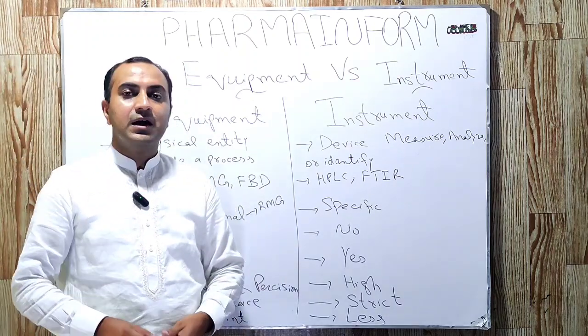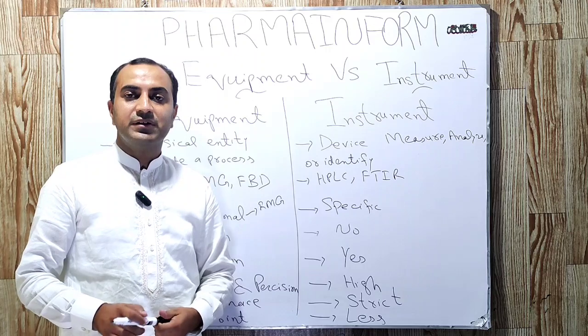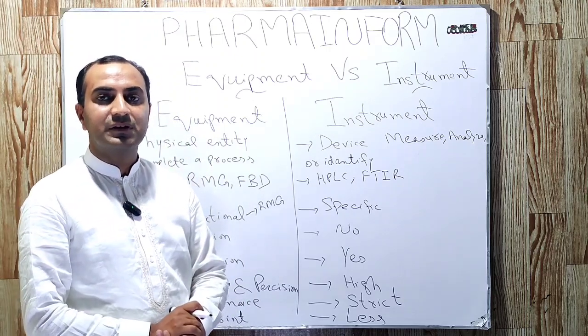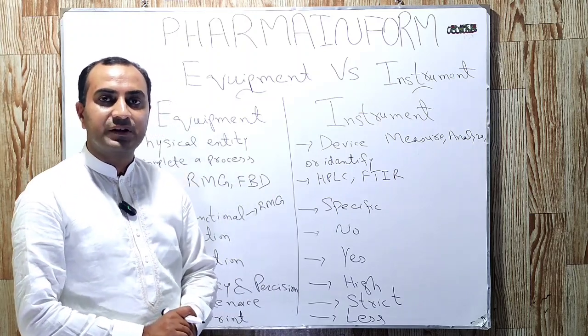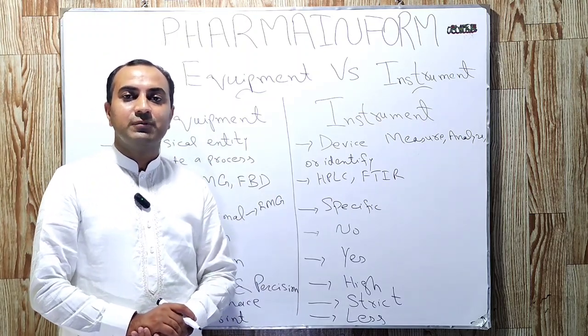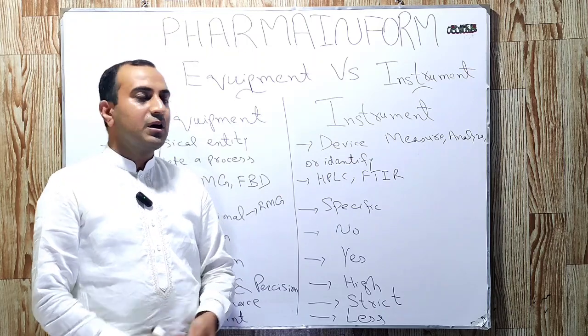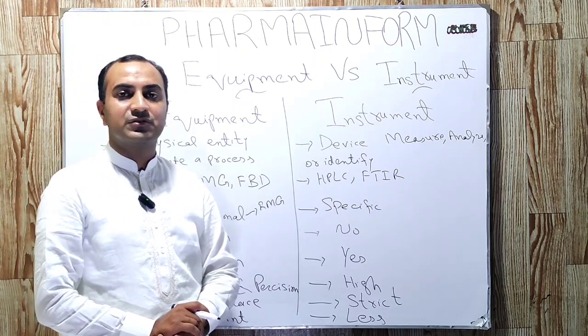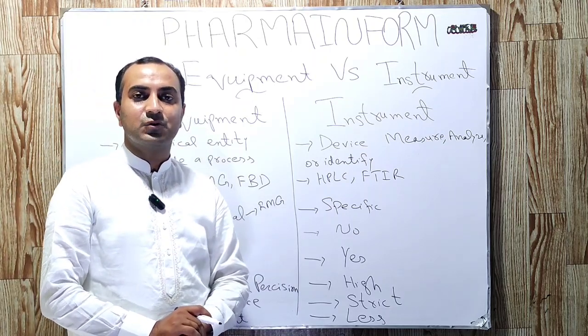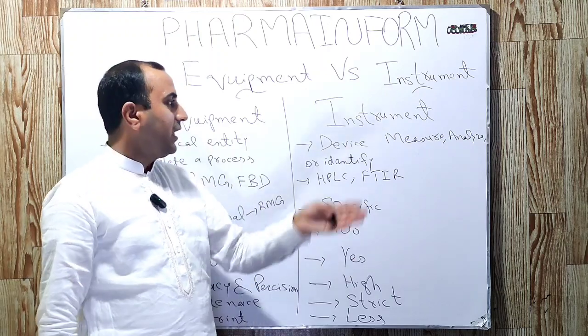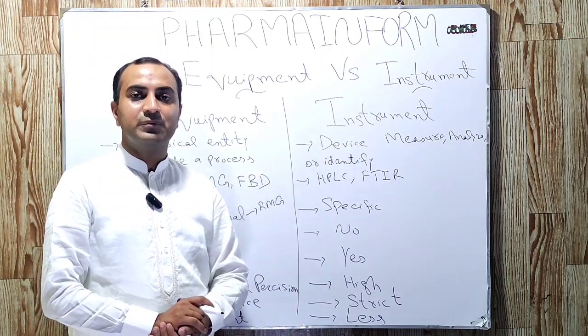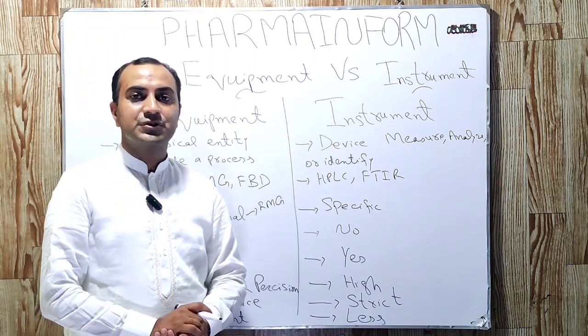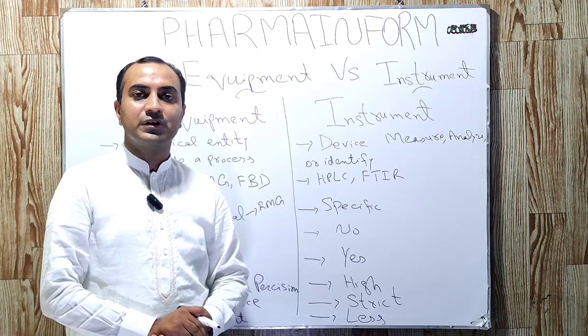The next difference is maintenance. The maintenance schedule for equipment has some leniency — we can skip maintenance for one day or some time and perform it later. But for instruments, delay in maintenance is not acceptable, because if maintenance is not performed on time, the results will be challengeable and may be compromised. So maintenance and calibration for instruments must be performed on time.